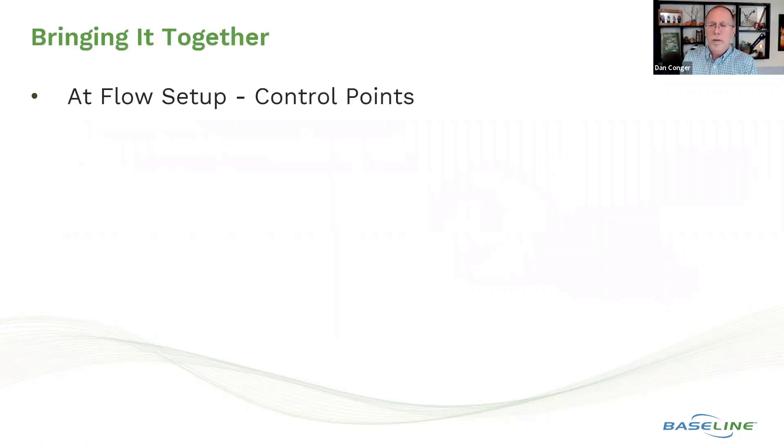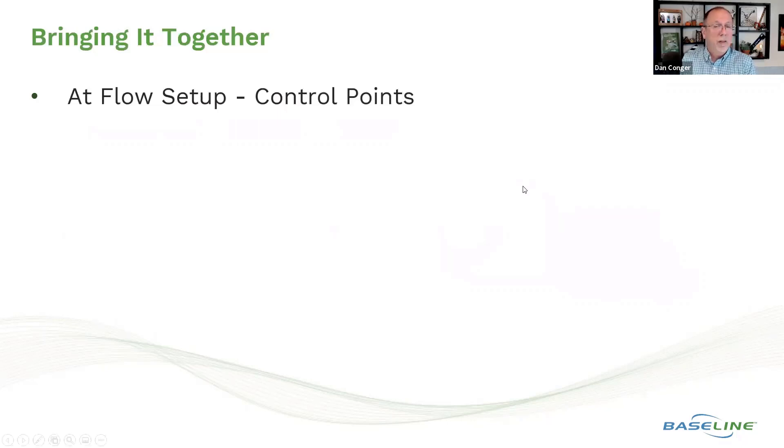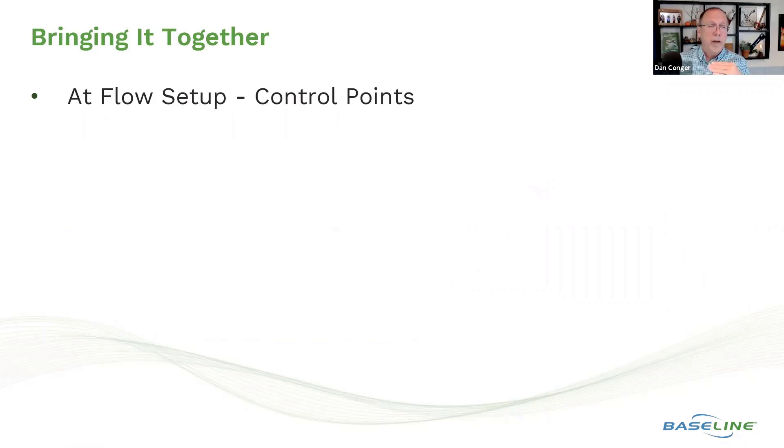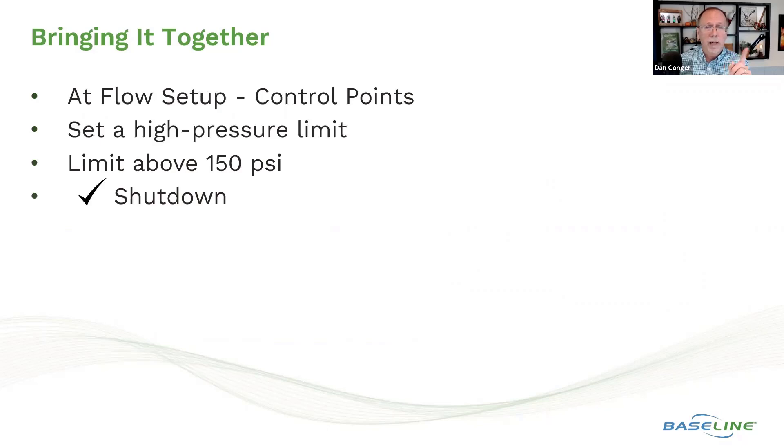So for programming this, we're going to do this at flow setup control points. We're going to do this at the control point level because I want to influence everything downstream of that master valve. I'm going to set a high pressure limit. The limit's going to be 150 psi and I'm going to click shut down.